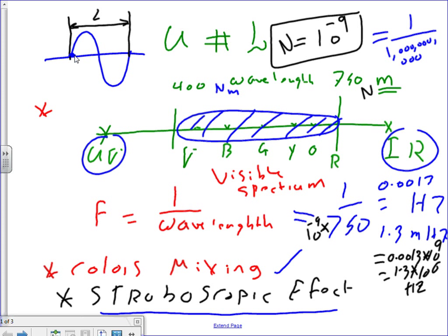We know the stroboscopic effect is a deception of the light, where a rotating object appears still in one phase. If you add multiple phases, they reach zero at different points in the cycle. If you have three signals like this, it basically eliminates the stroboscopic effect. Any comments, any questions? That's a major thing on the manufacturing floor.